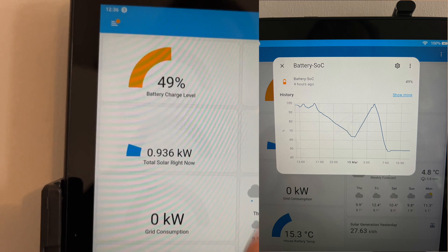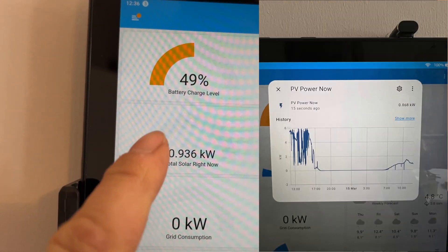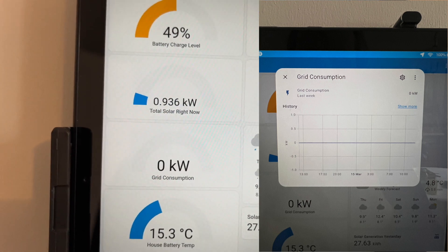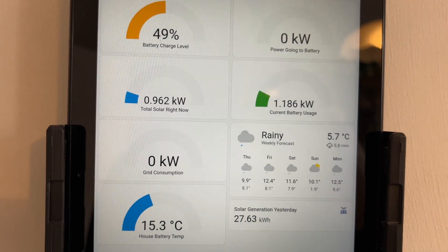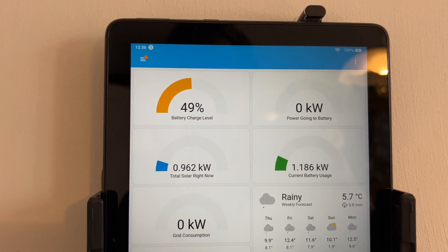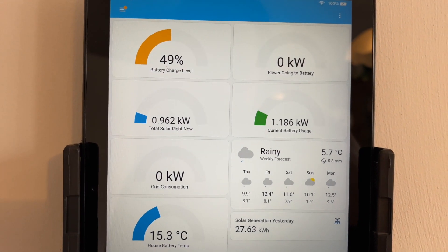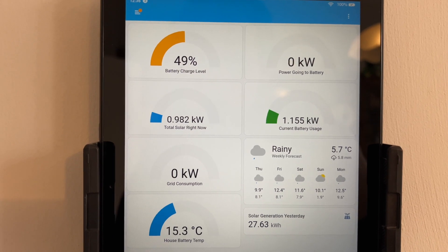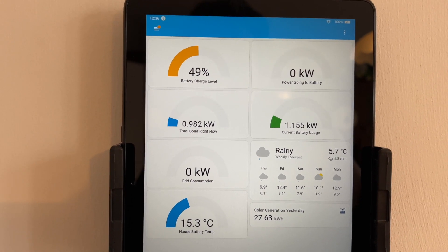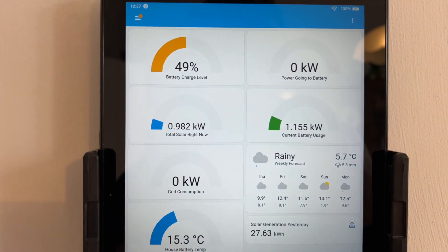Something a bit odd — this wasn't reporting, and that wasn't reporting. Essentially it hasn't worked for four hours, so it hasn't been reporting back for about four hours. It's now 12:00 — it went off about 8:30. The BMS went a bit jittery about 8:30, so it's back to where it should be. But sadly, whilst the oven and everything's been on, this hasn't been reporting.